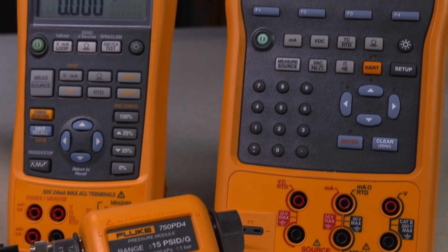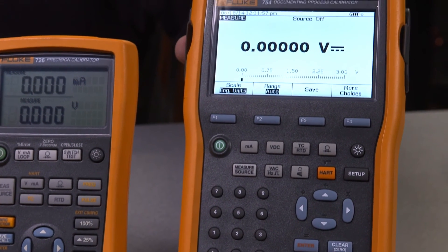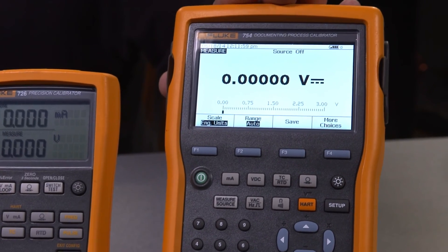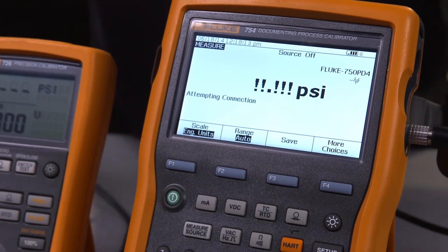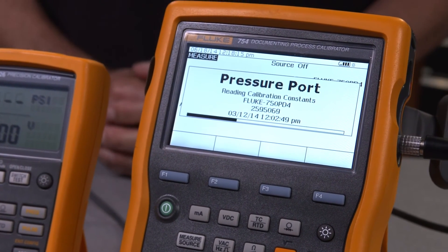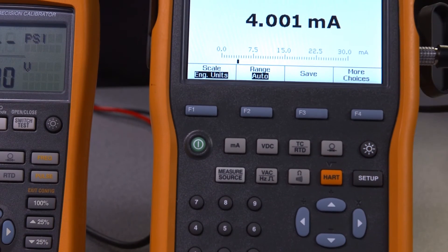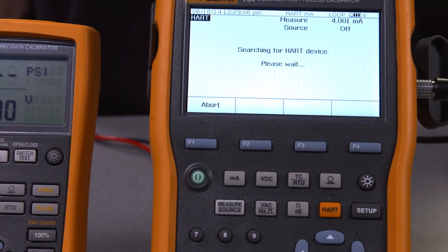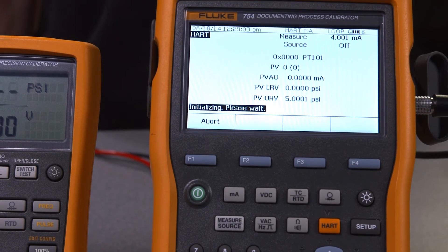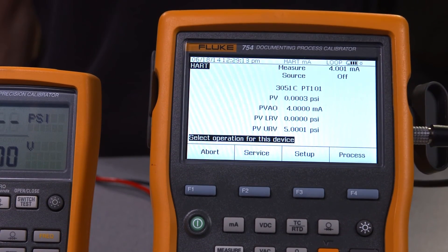For the challenge of documentation, the 753 and 754 documenting calibrators paired with the 750 series modules and DPC Track 2 calibration management software create a complete documenting pressure calibration solution. Got HART instruments to calibrate? The 754 includes HART communication capability onboard so you can perform light configuration of HART pressure devices and make trim adjustments on the transmitter sensor or milliamps.